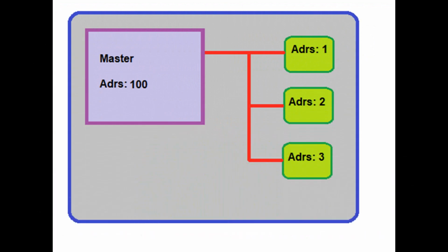Each device in a DNP3 network, both a master and each outstation, is assigned a 16-bit DNP3 address. Each DNP3 message contains 2 addresses, one for the device originating the message, called the source address, and one for the device where the message is destined, called the destination address.